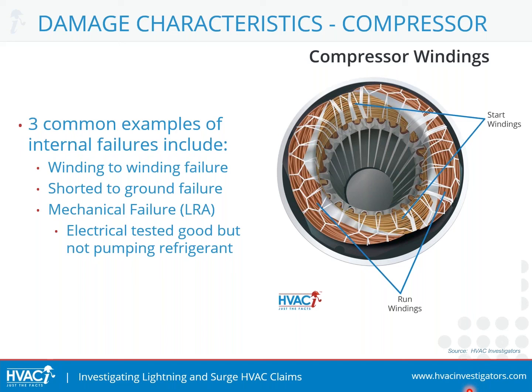The number one cause of that is a lack of refrigerant. We've had a leak over time, the system hasn't been well maintained, and we've lost refrigerant. The refrigerant has the oil in it, and the viscosity of that oil is what lubricates the motor to run. If you think of your car — if you run your engine out of oil, it's going to seize up and lock up. The same thing happens with this electrical motor. If we have a lack of refrigerant, we can get LRA — locked rotor amps.